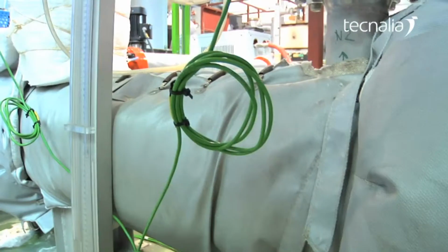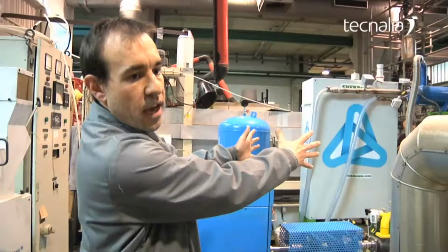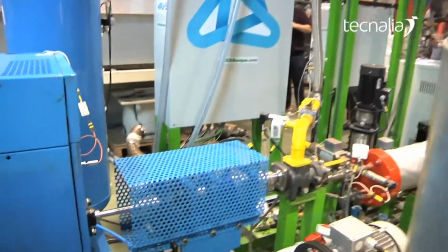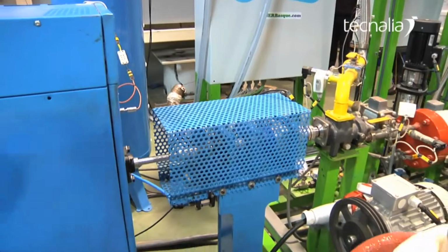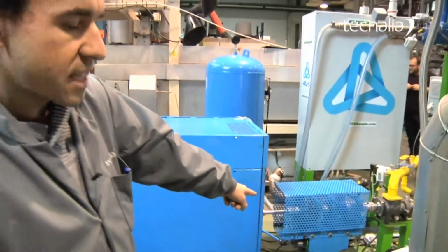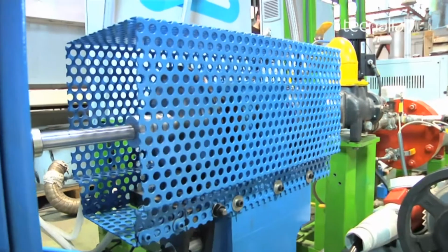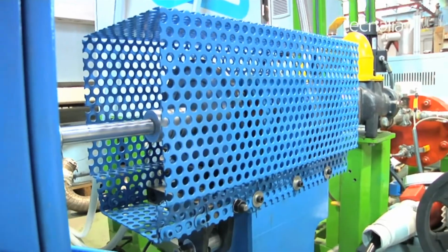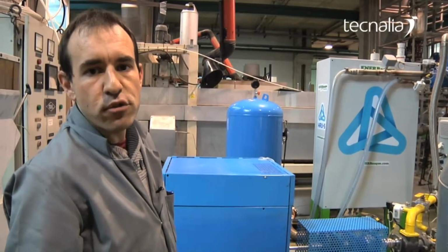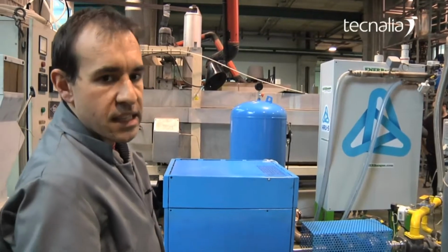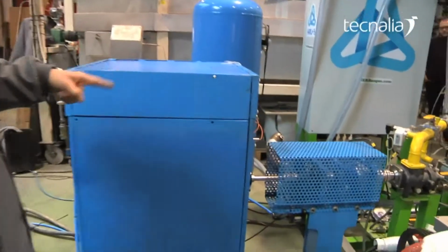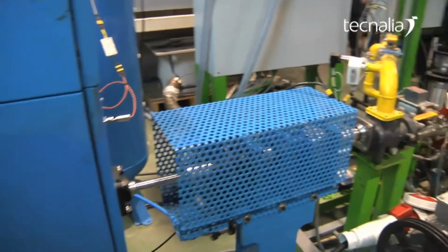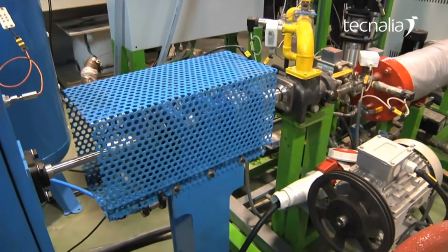Once the water is heated, it goes to the ORC system where it delivers the heat to the organic fluid in order to activate the transmission system that we can see here. This is the transmission system that is generating mechanical energy, and the shaft is rotating at around 6,000 RPM. Then, with this velocity, we are activating the compressor in order to generate compressed air, as we will see now.